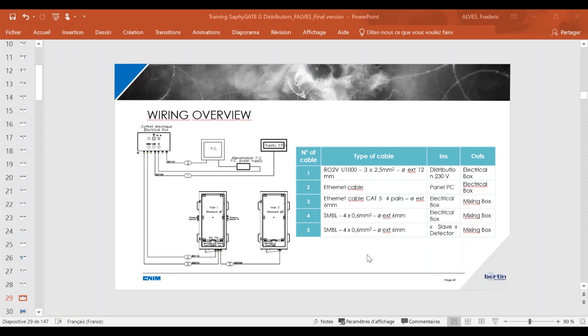I was telling that cable 2 is the Ethernet cable between the panel PC and the electrical box, and the third one is the cable between the master detector and the electrical box. In fact, you have two cables between the electrical box and the master detector: cables 3 and 4, one being the Ethernet cable for communication, the other an SMBL cable for the supply of the detector. The last cable is between detector 1 and detector 2, master and slave detectors, and this cable is for communication and also the supply.